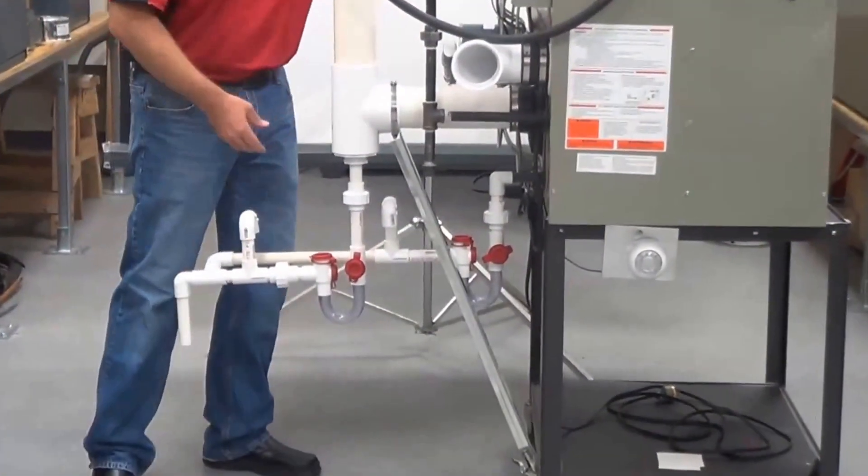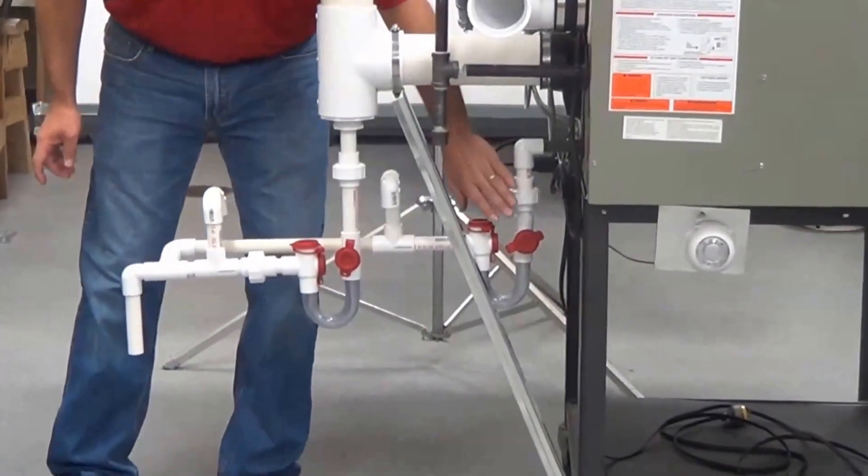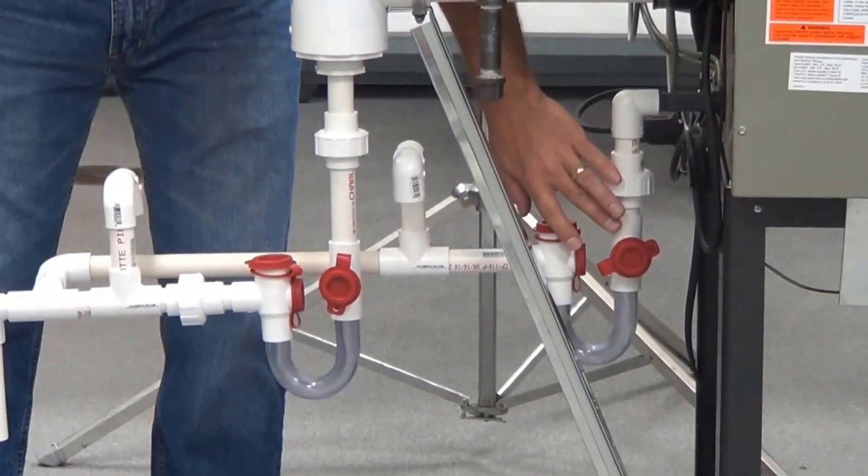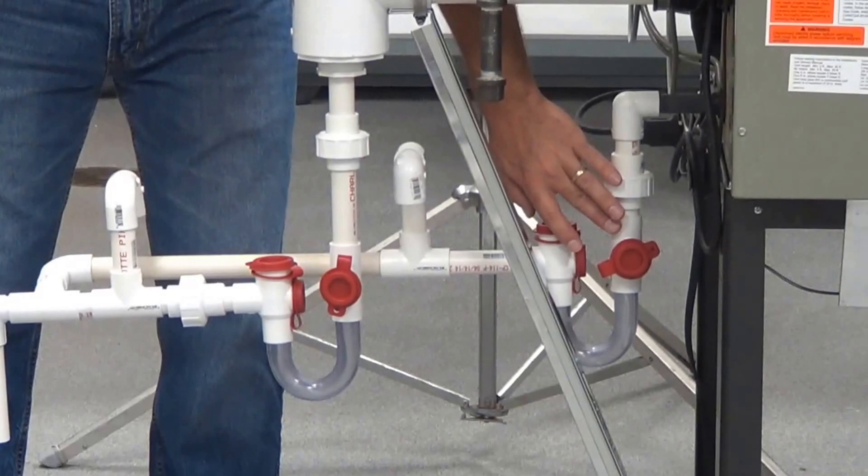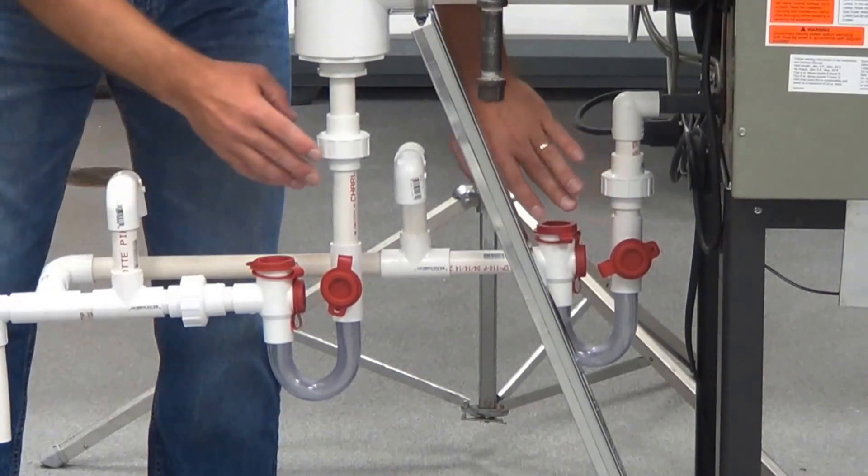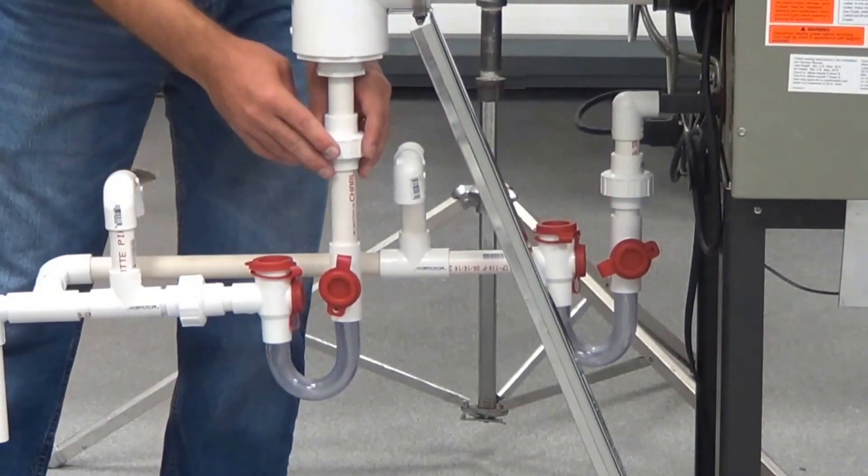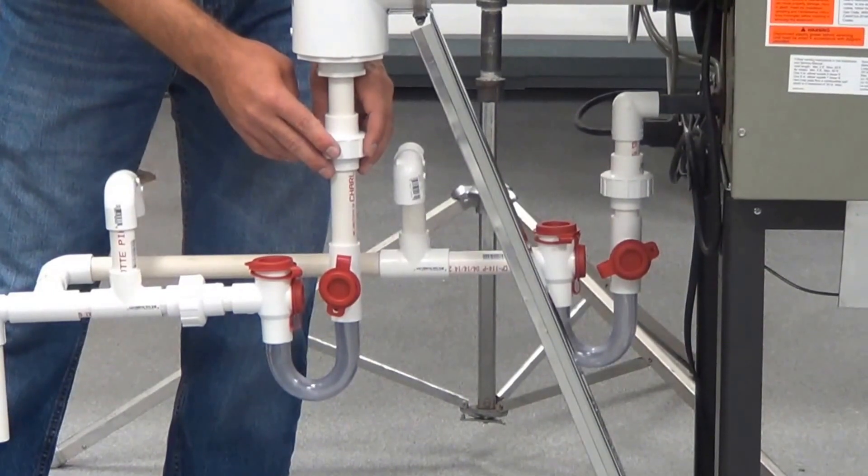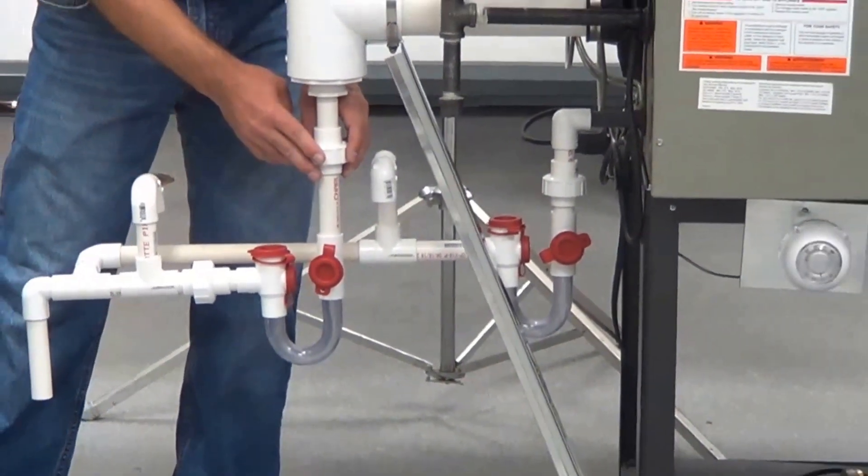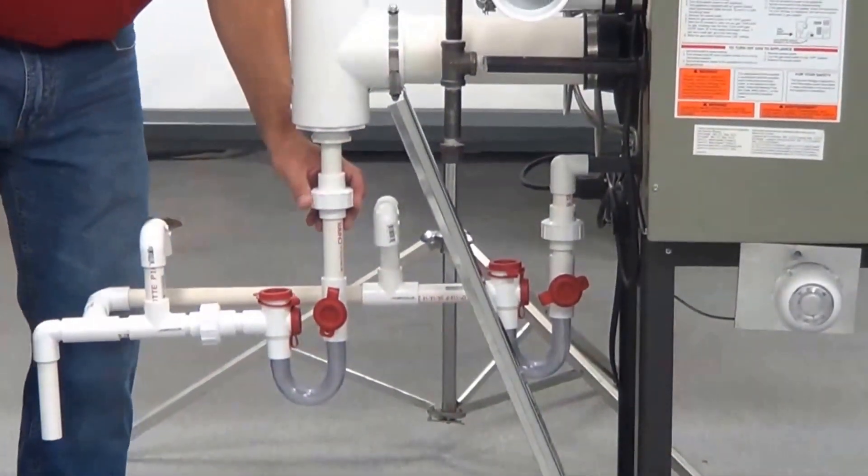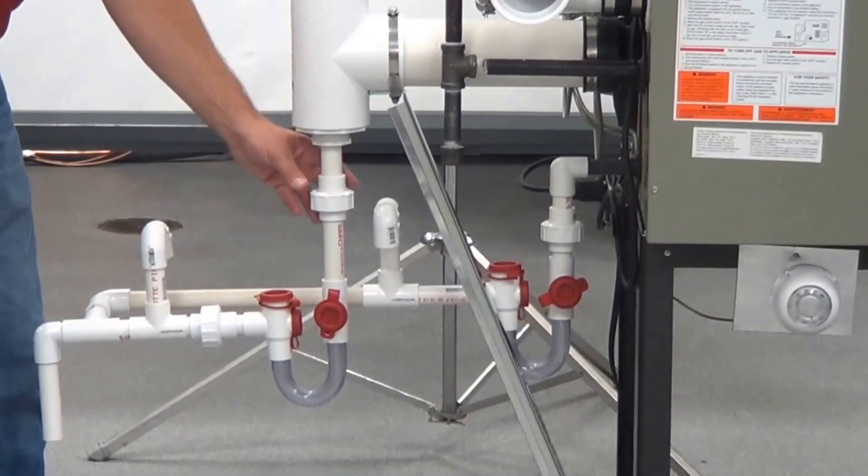So what we have here is we have a condensate from the lower side, which is from our secondary heat exchanger. And we also have a condensate from the vent pipe. So it's critical that you install both condensate traps, one on the secondary drain side and one on the venting side.